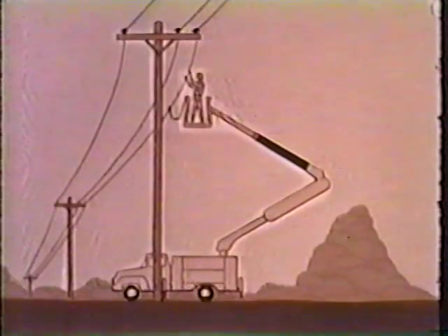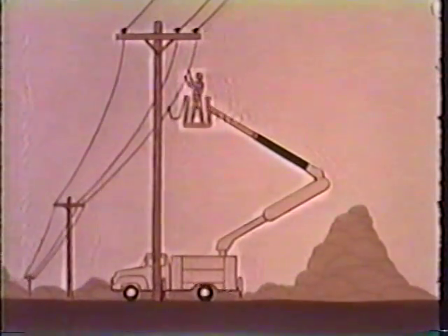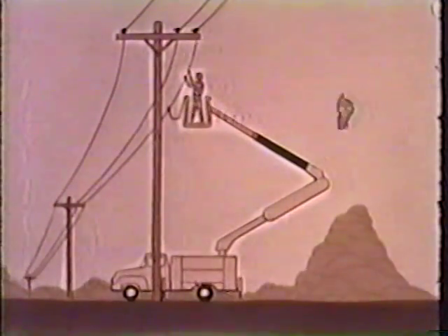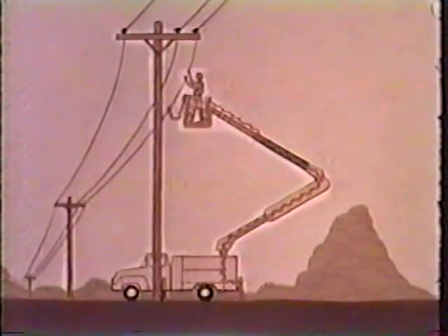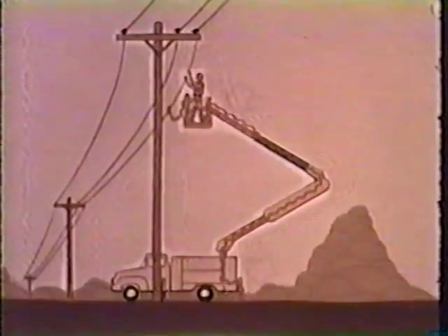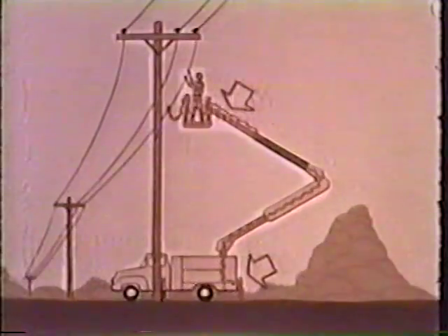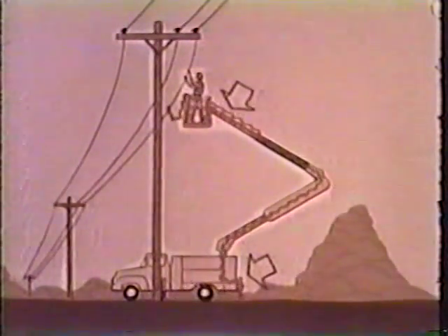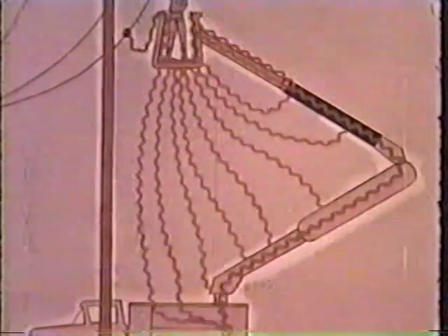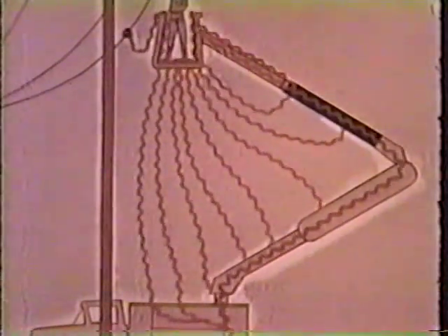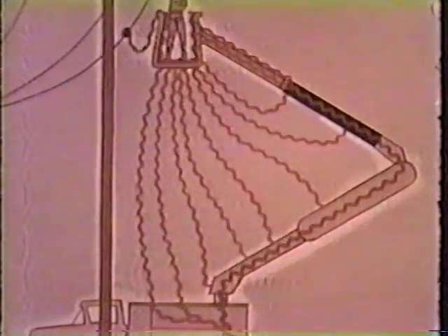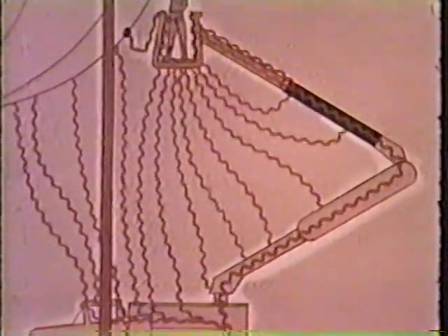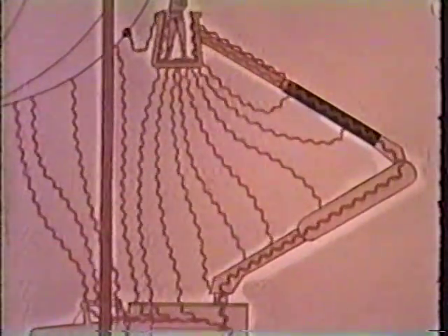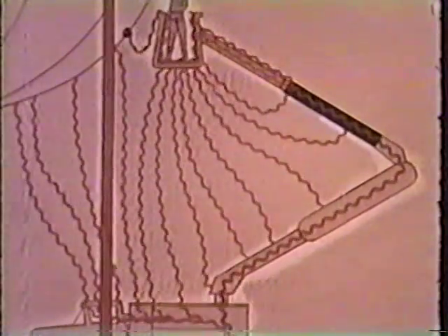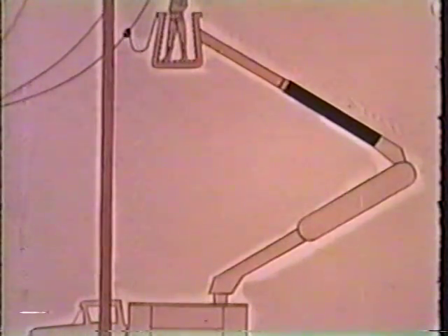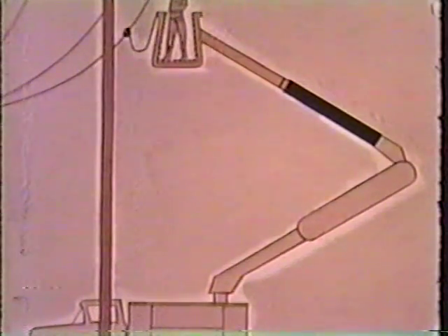In performing live line work by the barehand method, it is essential to be able to determine, and under severe weather conditions to monitor, the amount of current flowing along the insulating arm. This arm current cannot be measured by placing a meter between the truck and ground, because a meter at this location would include not only the arm current, but also stray charging currents which shunt the arm and pass directly from the bucket shielding to the truck body and from the conductor itself to the truck body. The Holland aerial elbow provides a method for measuring the arm current, a method which eliminates from the measuring circuit the large stray capacitance which shunts the arm.